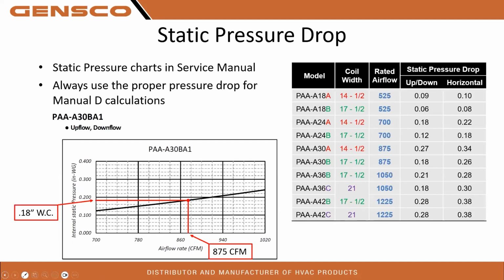Static pressure drop. So when you guys are sizing these things up, this will be an important one to make sure you get your static set up correctly. If you notice on our chart here, we have an A and B, it's highlighted in green and red. Those are for your coil width. So make sure you're paying attention, when you're setting up or calculating your static, that you're using the correct coil width.